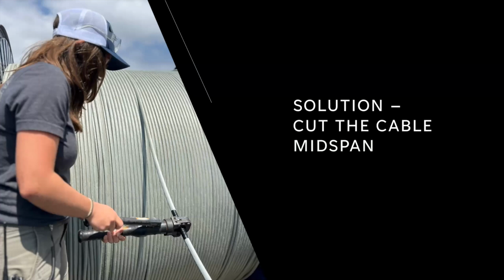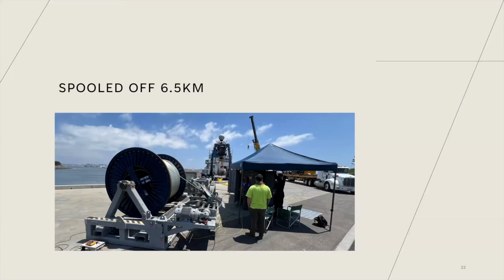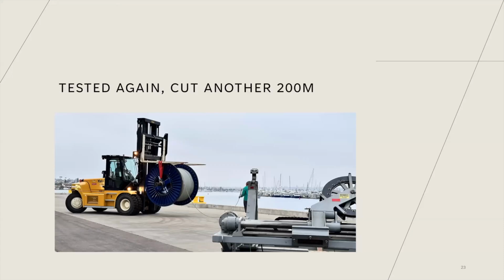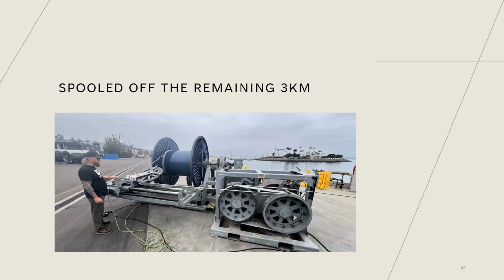That's what we did. We came back into port and we cut the cable mid-span. So this is us at the Scripps Pier. We spooled off 6.5 kilometers of cable. We remeasured it and narrowed in, and we found that now only one of the conductors was included in the fault. That's how we knew that there were two different faults. So we narrowed in on that last 200 meters, cut the cable a second time, tested it with a measure to make sure that all the insulation was good. And we forklifted it out of the way to get ready for the next 3,000 meters.